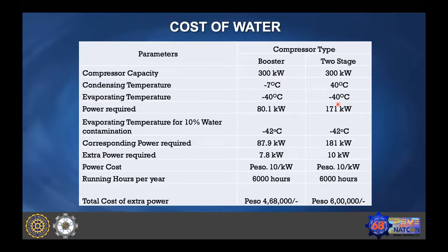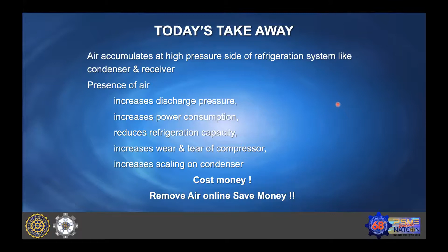So what are today's takeaways from the presentation? Air accumulates at the high pressure side of the refrigeration system, like condensers and receivers. The presence of air increases the discharge pressure, increases power consumption, reduces refrigerant capacity, increases wear and tear of the compressor, and increases the scaling on the condenser, and it all costs us money. So we have to remove the air continuously, preferably online, so that it saves us money.